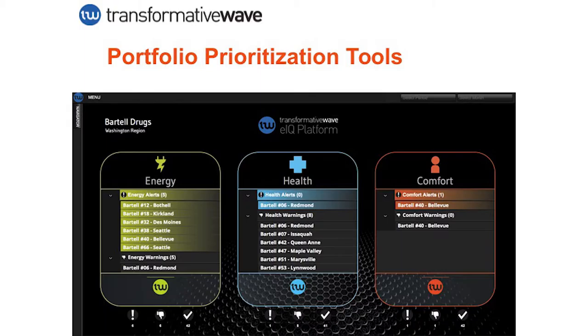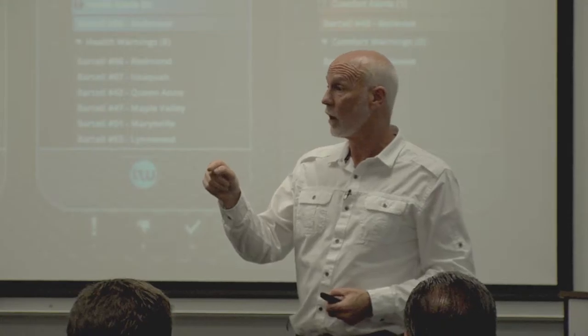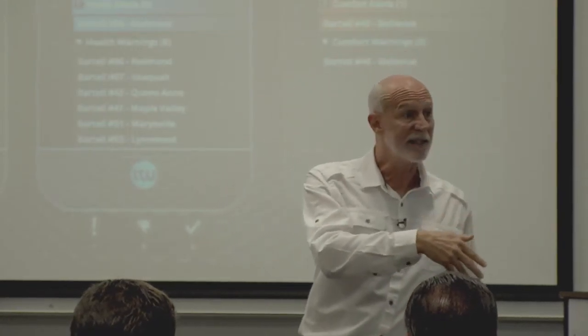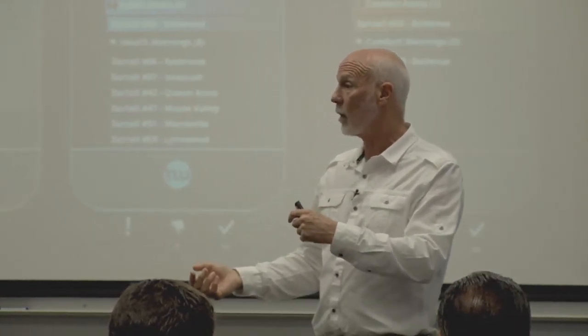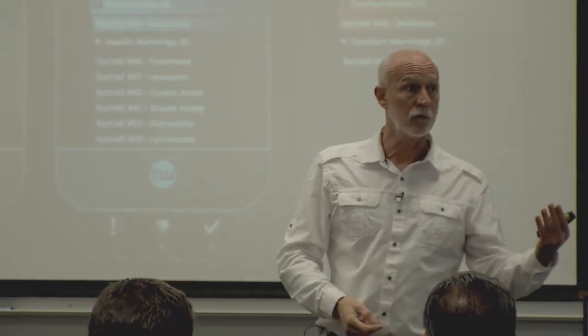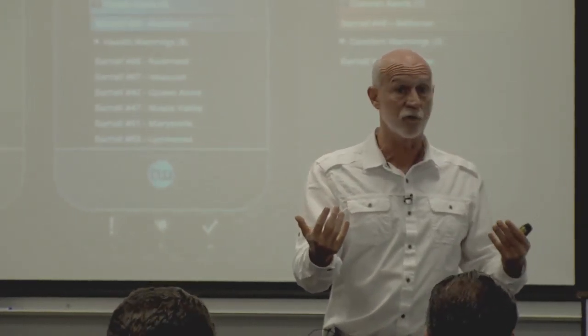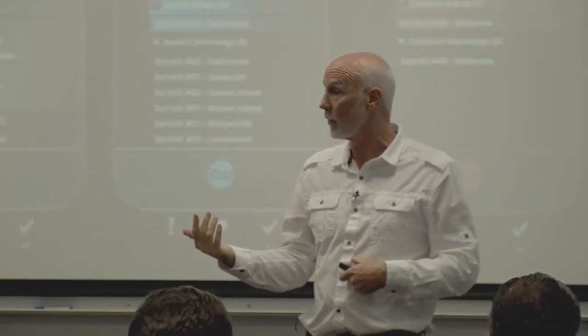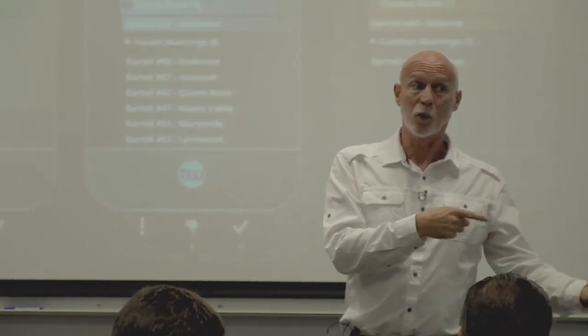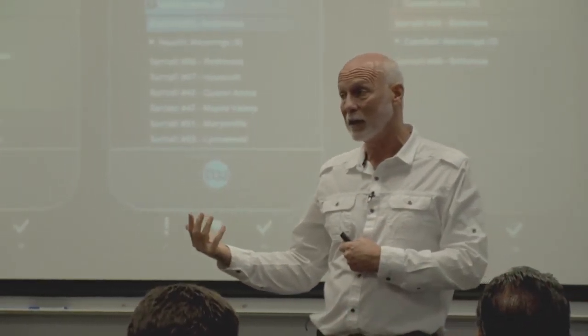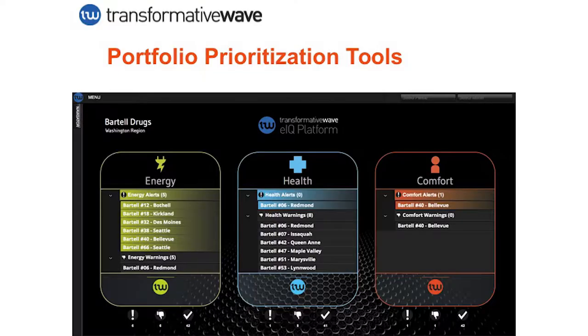That's where you can do your diagnostics, reset things, cycle things off and on. Is there power being consumed at the compressor, so we know the compressor's running and we're not getting good cooling out of it? Or is it being told to operate and it's not using any energy? Well, now we know the compressor's not running, it's probably off on a safety. That changes who we send and what we send them with when they go out and respond to your site.